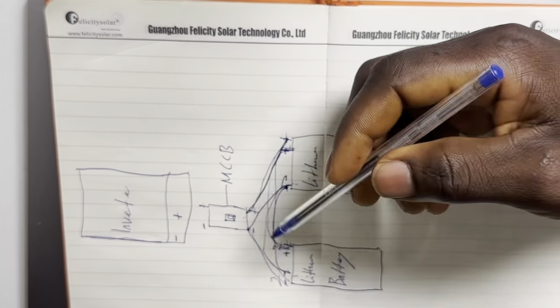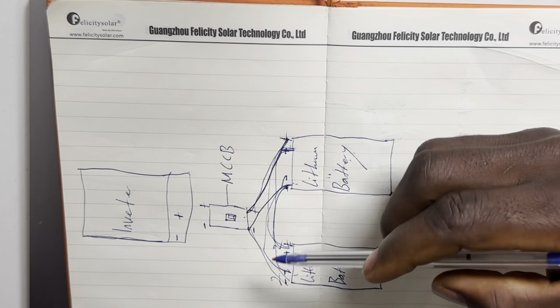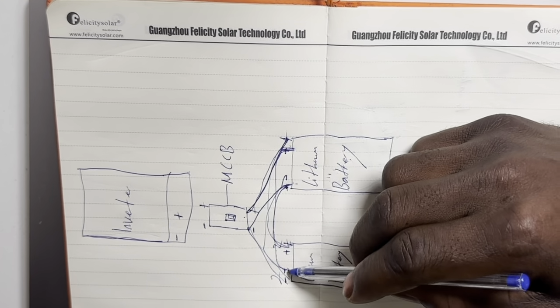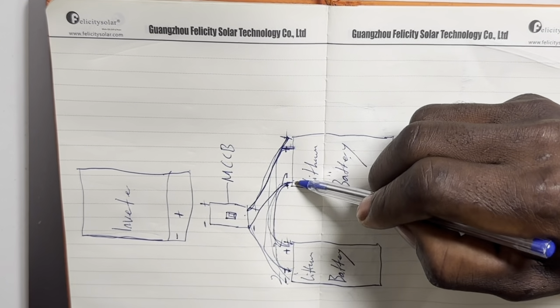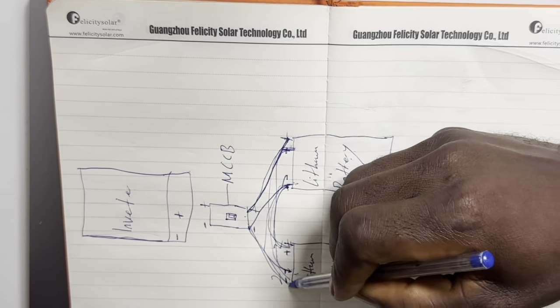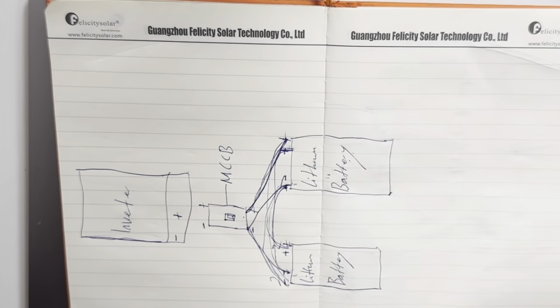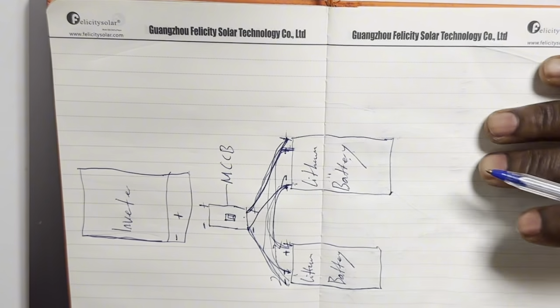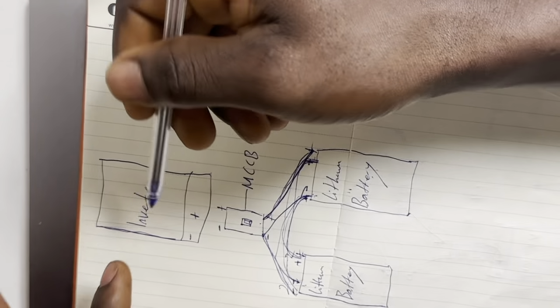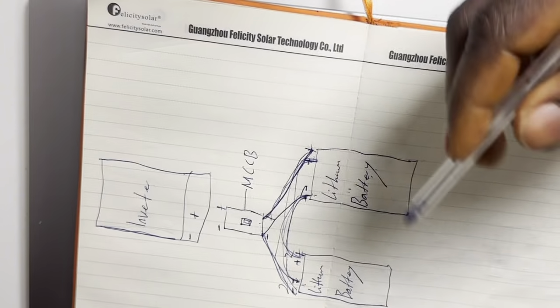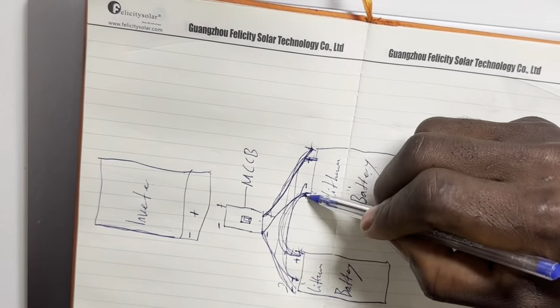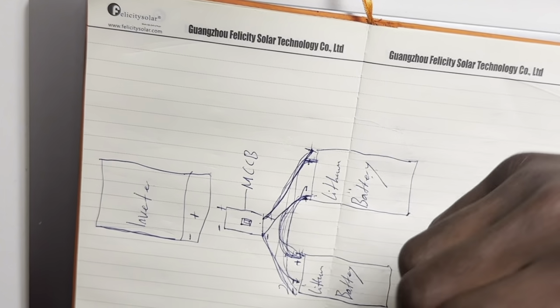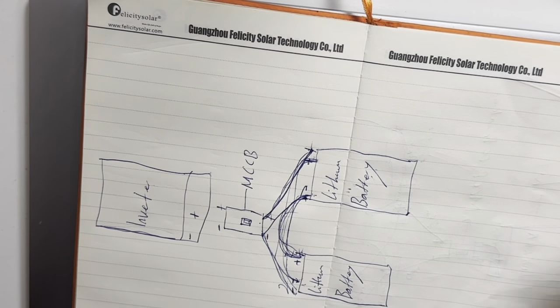As you're looping, if you use 36mm or 35mm to loop this to this place, make sure the cable going this way and this way are 50mm. The same principle applies because this battery comes with higher current, more than what this cable is rated for. So you definitely need a bigger cable to serve this battery. Otherwise you overstress the cable, which can lead to fire outbreak or the cable overheating. That is that.